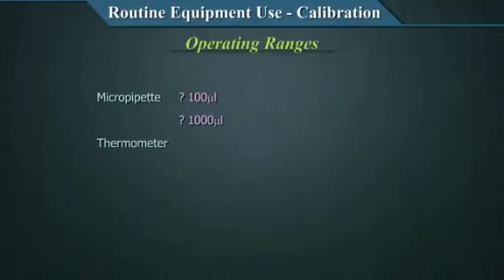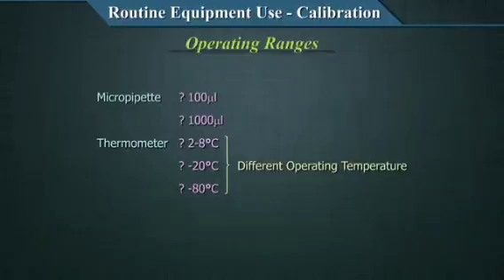Or suppose you're looking at a thermometer that you're using to measure a fridge temperature, which is to be between 2 to 8 degrees or minus 20 or minus 80, whatever it is. Please make sure that when it's getting calibrated, these operational temperatures are calibrated, and ask what the uncertainty there is. The thermometer may be able to measure up to 100 degrees or 60 or 70 or whatever, but it's not relevant for you. Your fridge thermometer has to measure and be very sure of the uncertainty between 2 to 8 degrees. Similarly, for a water bath, your 37 degrees centigrade is important. So that is how you decide what your operational requirements are and what the uncertainty there is.